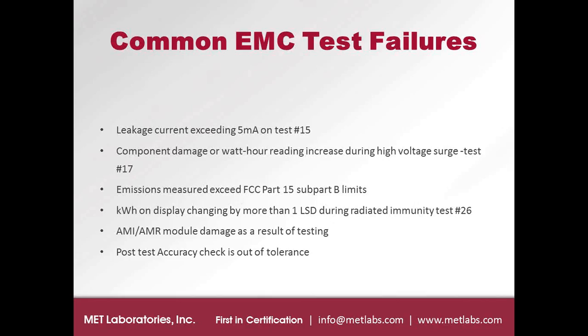The other issues that we see are component damage or watt-hour readings increasing during high voltage surge tests. During this test we see burnt out components and burnt out tracks. Sometimes the watt-hour readings that we are required to monitor during the test randomly fluctuate and increase.